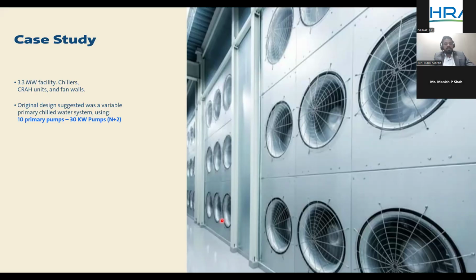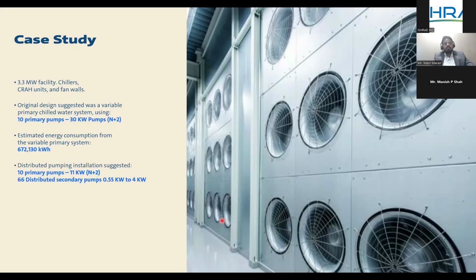The original design suggested was variable primary, with 10 primary pumps of 30 kilowatt each with N+2 redundancy, Tier 4. The estimated energy consumption with variable primary is around 672,000 kilowatt hour. With the distributed pumping design, where we removed the unnecessary friction and have dedicated pumps, 66 in number, connected to each unit, and 10 primary pumps where the primary head reduces and the power reduces to 11 kilowatt.